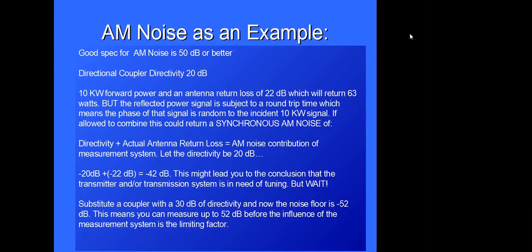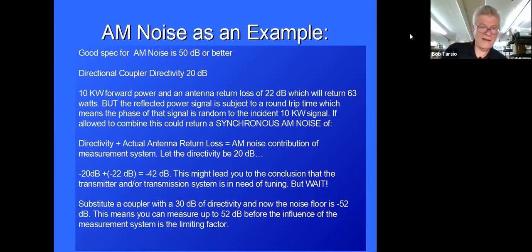I just heard a bell go off. Now you have a noise floor of 52 dB. So you were never going to measure anything better than 42 dB with the 20 dB coupler, but now you can see at least a 52 dB noise floor. So your dynamic range of measurement has been improved by at least 10 dB, and you can actually see what the transmitter is doing at that point. So it's not a limiting factor.